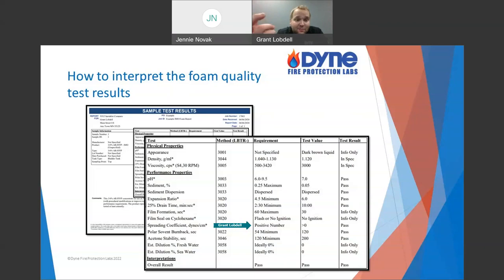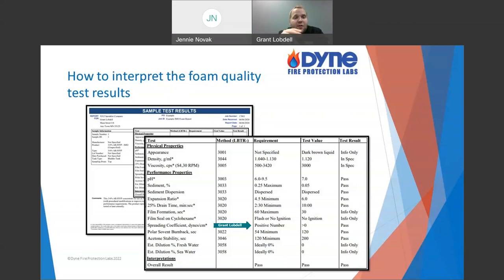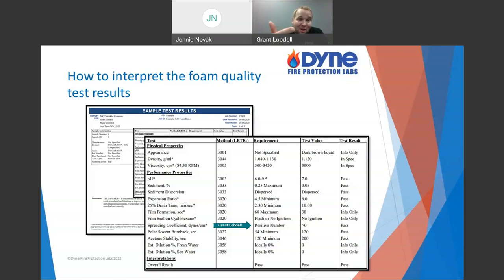Why would a spreading coefficient be negative — why would it fail? Again, dilution, age, and storage conditions. Another big one: was it actually a film-forming foam? We've had foams where people assume AFFF just means foam and call everything AFFF. Nowadays we also have SFFF — synthetic fluorine-free foams — which are not film-forming. Naming is very important. What you tell me it's supposed to be is very important to what I compare it to.